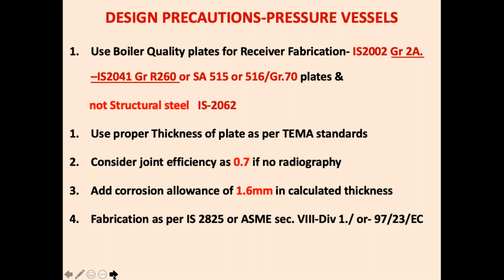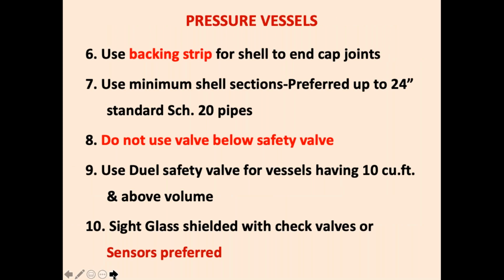Use proper thickness as per TEMA standard, Tubular Exchangers Manufacturers Association. Consider joint efficiency of 0.7 if you are not doing radiography. Add a corrosion allowance of 1.6 mm to the calculated thickness and then provide the vessel thickness. Fabrication as per IS 2825 or ASME Section 8 Division 1. This is important. The next is use backing strips for shell and end plate.